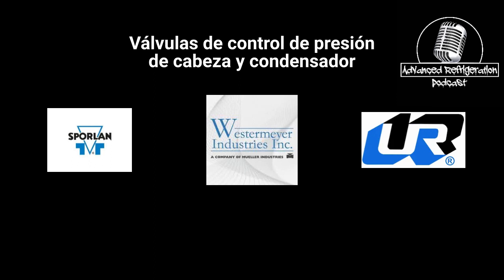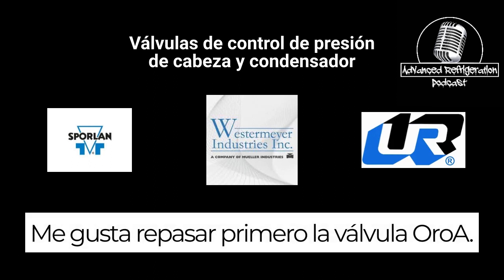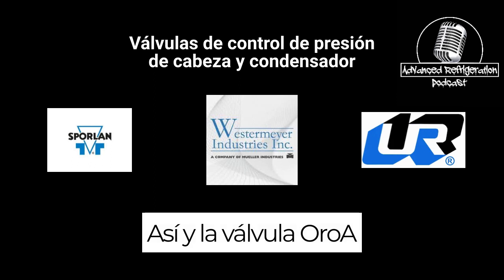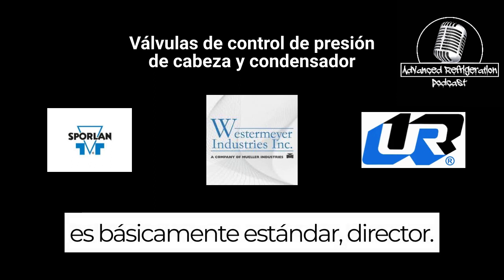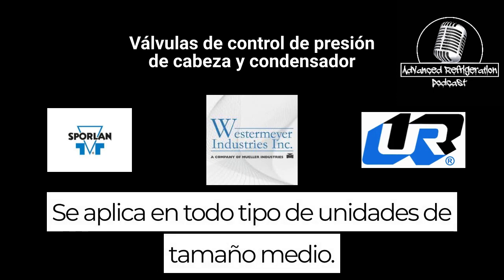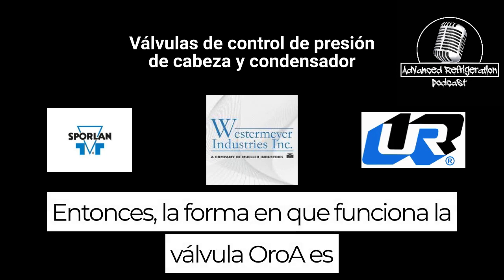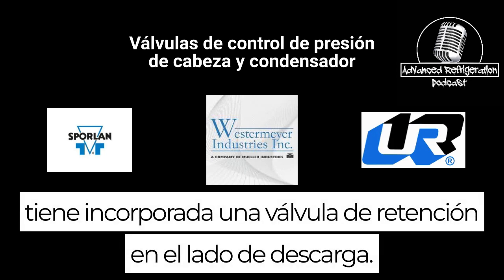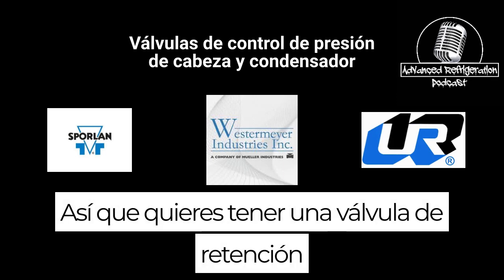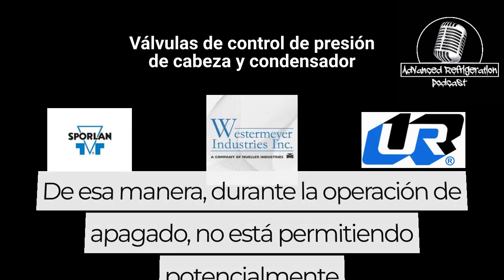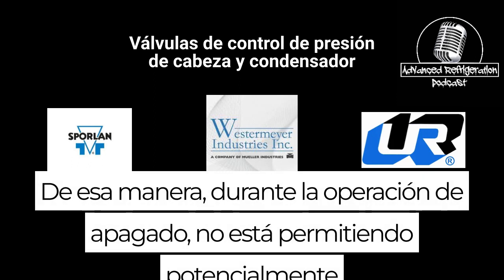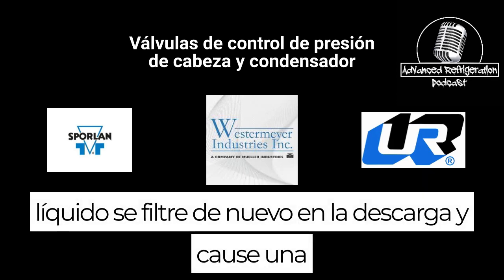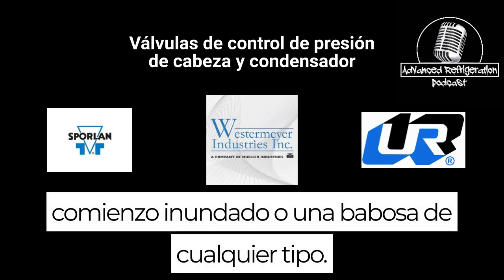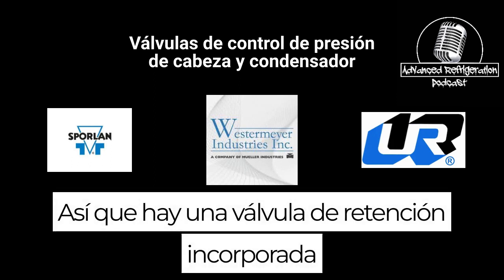So I like to go over the ORO valve first. The ORO valve is basically a standard headmaster. It's applied across all kinds of mid-sized units. The way the ORO valve works is it has a built-in check valve on the discharge side. You want a check valve on the discharge line of it, so that during shutdown operation you're not potentially allowing liquid to seep back into the discharge and cause a flooded start or a slug of any kind. So there's a check valve built in.